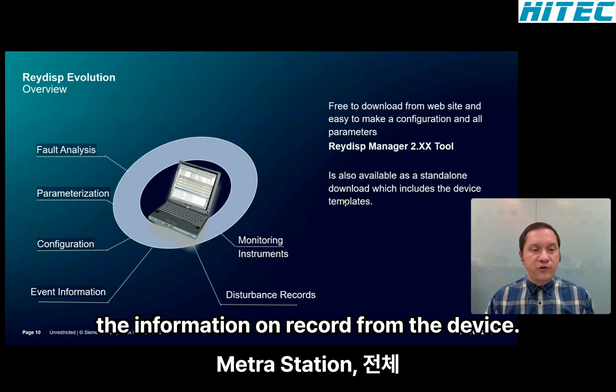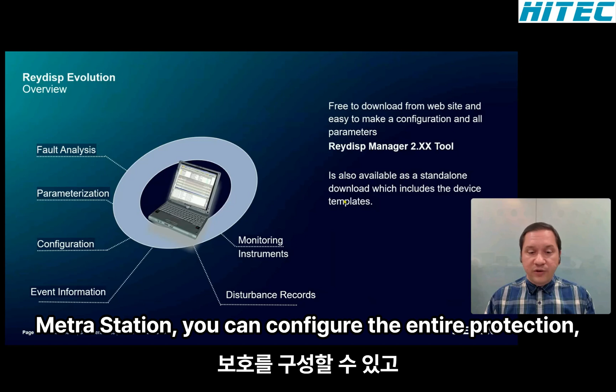So you can pull the fault information, waveform records from the device. You can do all your parameterization. You can configure the entire protection. You can get event information, and here it says disturbance records, which is actually waveform records.